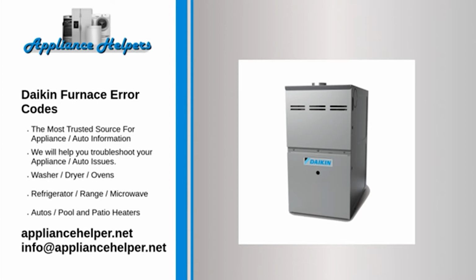Code: single LED flash. Problem: furnace lockout due to an excessive number of ignition retries. Fix: locate and correct gas interruption. Reset by lowering it for 20 seconds and then raising it back. The furnace will reset itself after 1 hour.